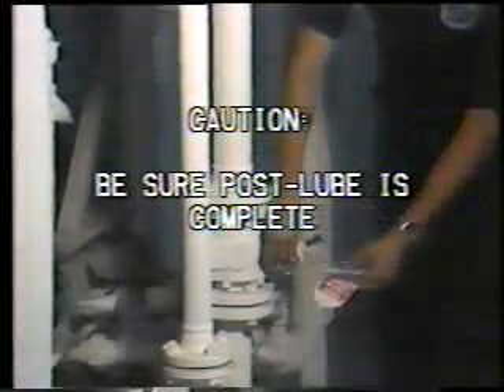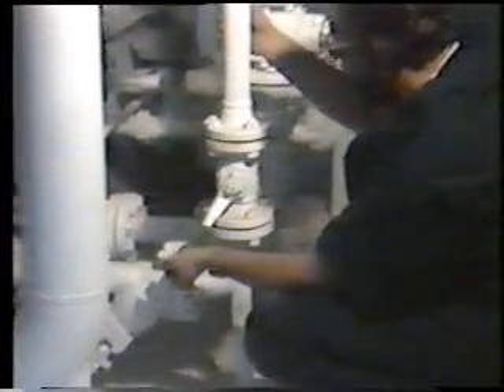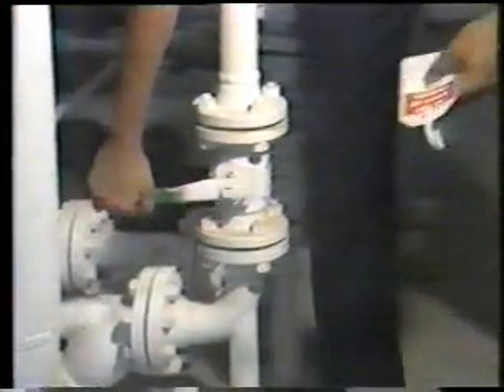Shut the unit down. Turn the master switch off and tag it. Caution: post-lube of the engine must be complete prior to securing the service gas or the electrical power which drives the post-lube pump. Turn the fuel and service gas off and tag the valves. On some units installed in the field, customer modifications may include a pilot gas shutoff valve. Secure this valve and tag when used.